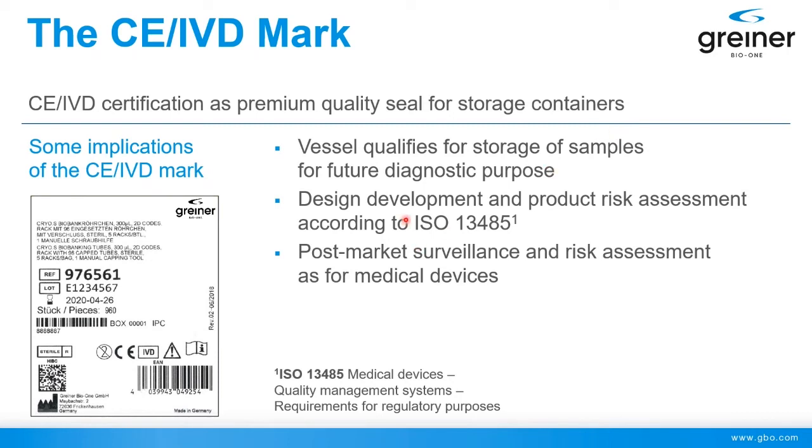I want to emphasize 2-3 things that happen if a product is developed and marketed which has the CE IVD mark. You first of all have to design the product according to the rules which also apply for medical products, and you have to do a risk assessment which you would also need to do for medical products.